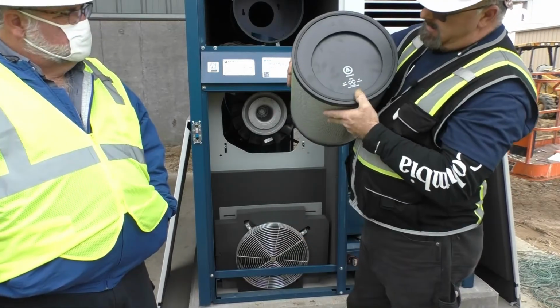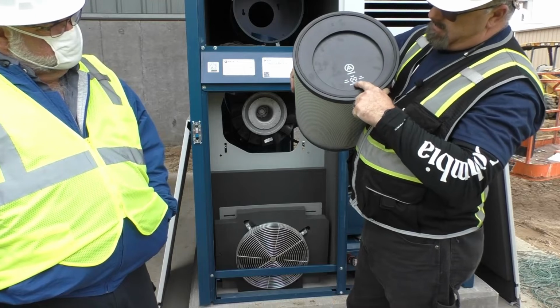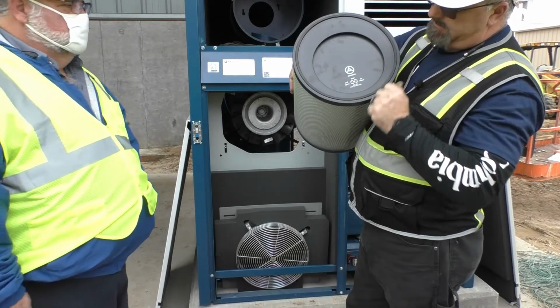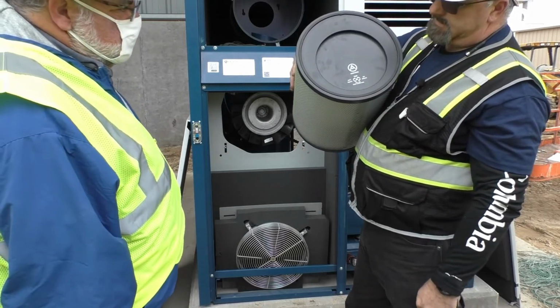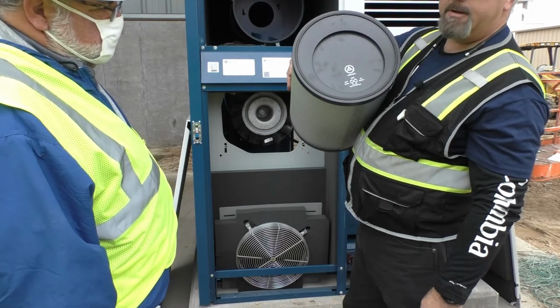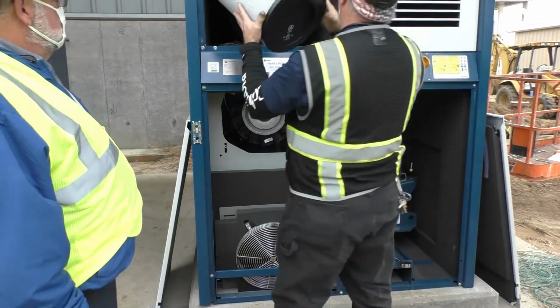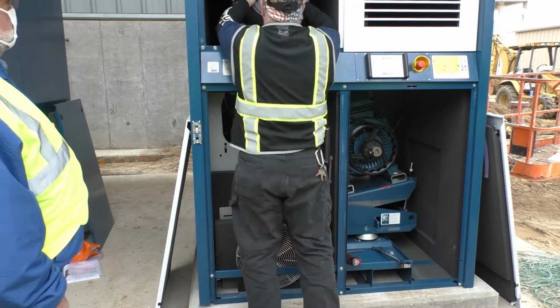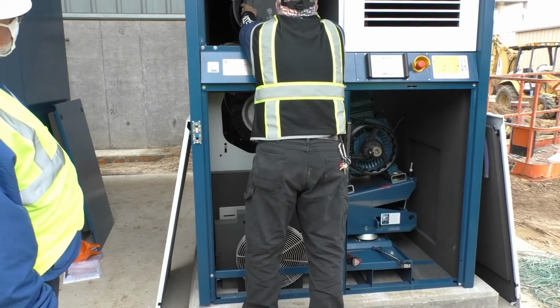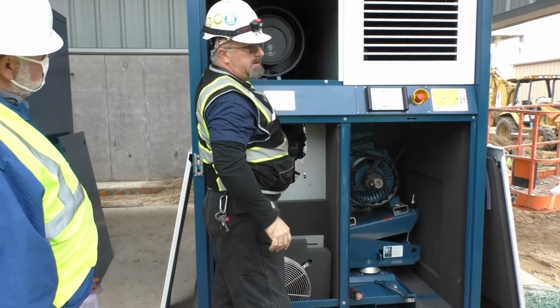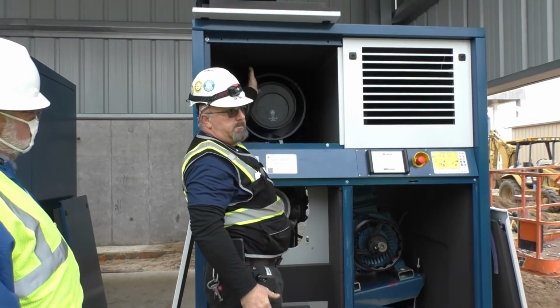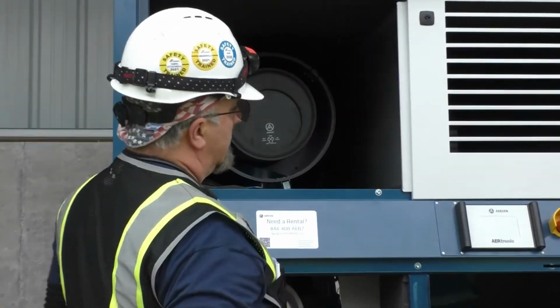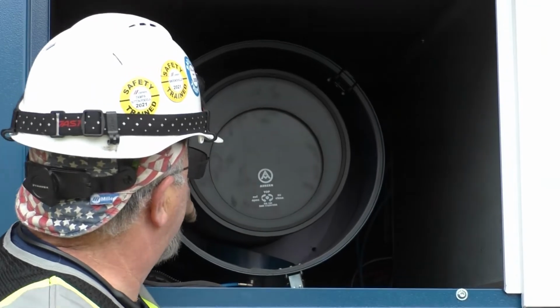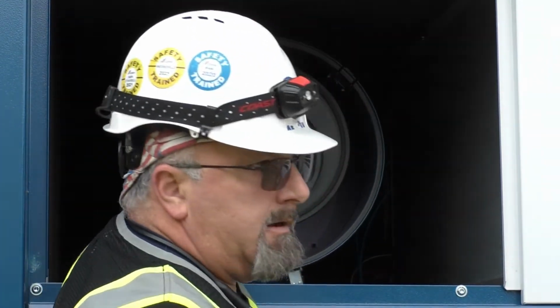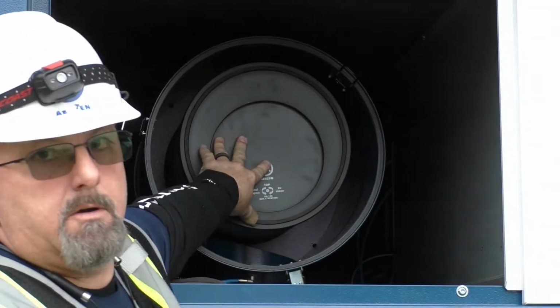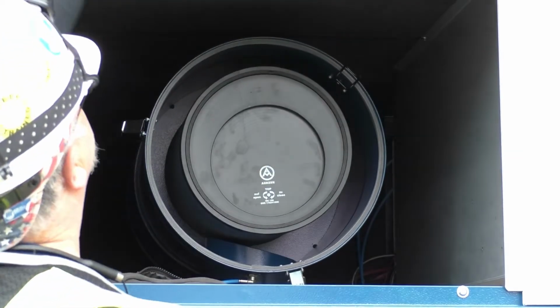So when you do an inspection, what you're going to notice is the airflow comes in this way and then flows out through the filter. So on the bottom down here, you're going to notice almost the same size as your intake pipe. It's going to be really dark in that one spot. Now, as it goes up toward the top, it will get lighter in color, but if it's really bad, then you'll want to replace it. And on the back of here, it gives you your part number, frame size, and it tells you what's the top and how to put it in and out. So we reach up in here, and like I said, it holds it in place while you're installing and removing the cover, but it doesn't seal it. Once you put the cover on, it pushes it up against the back, and this seal here is what seals it.